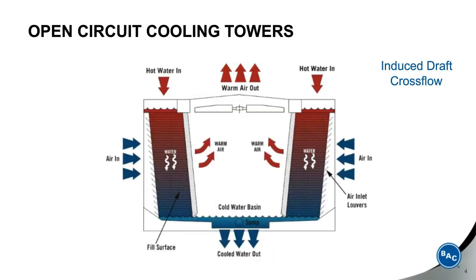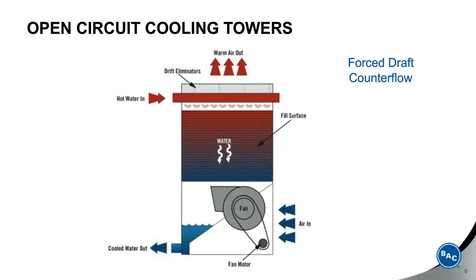The next type of cooling tower is an induced draft crossflow. This is a little different design. Basically, we're taking the hot water and putting it in each side of the tower where it falls over the fill pack by gravity. Air is again induced up through the cooling tower with the fan you see in the center of the unit, and the water is cooled and is collected in the water basin and then goes back out to the load. There is another type of cooling tower known as a forced draft counterflow cooling tower.